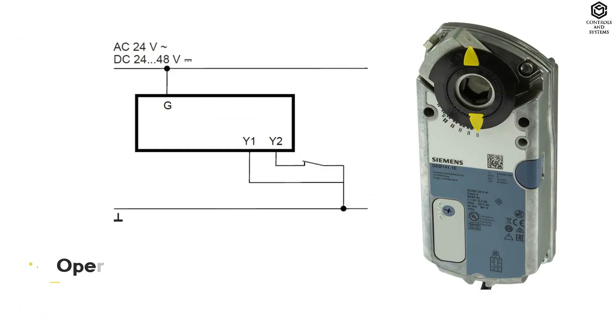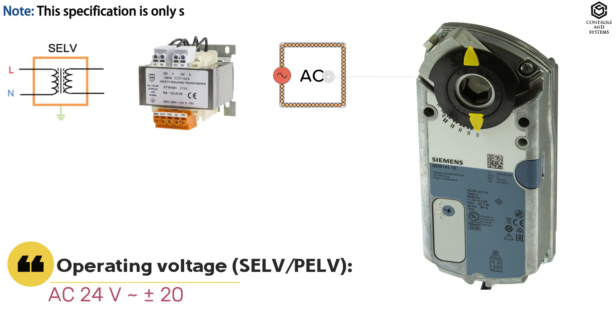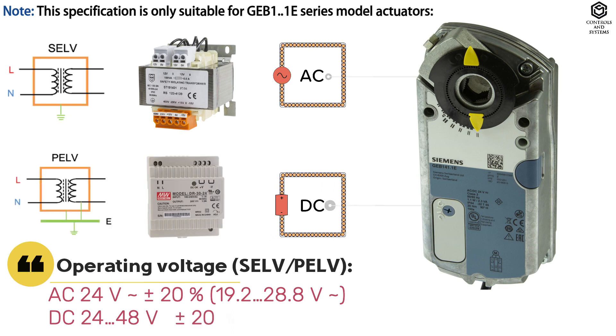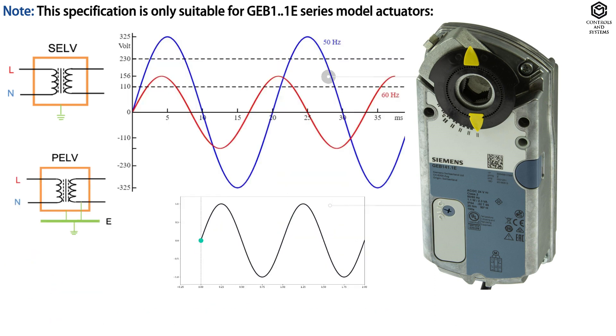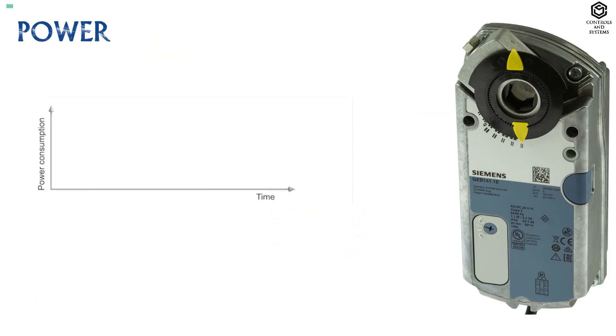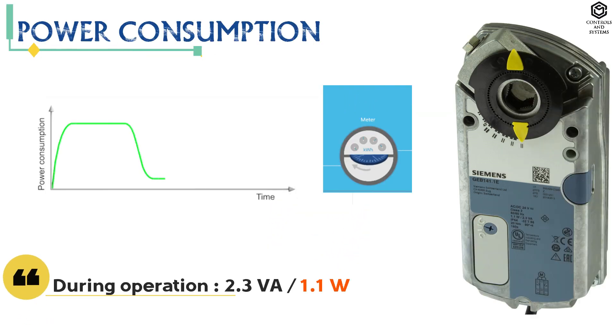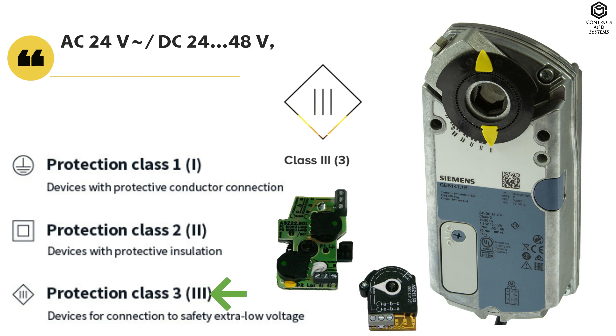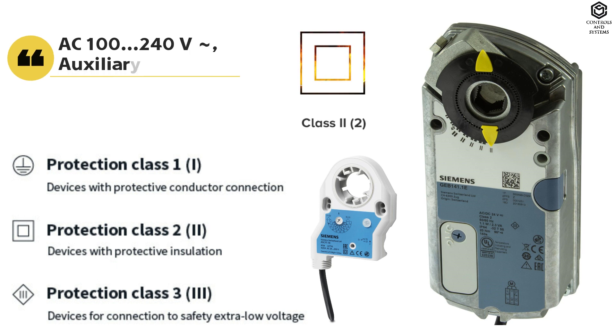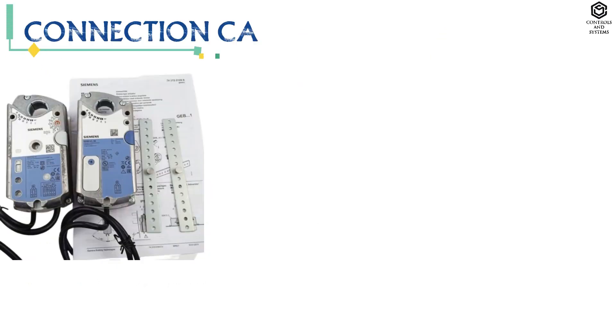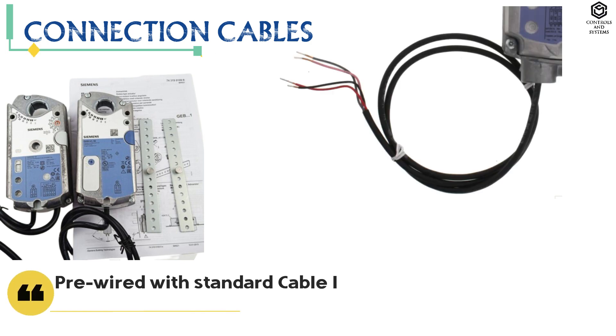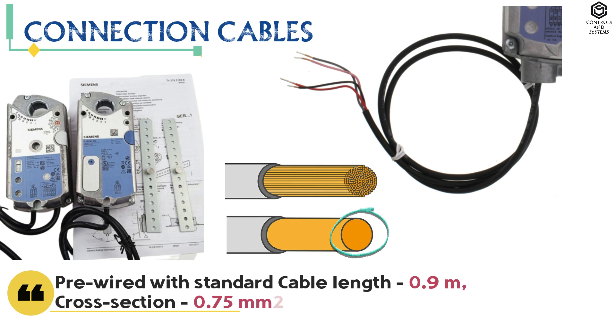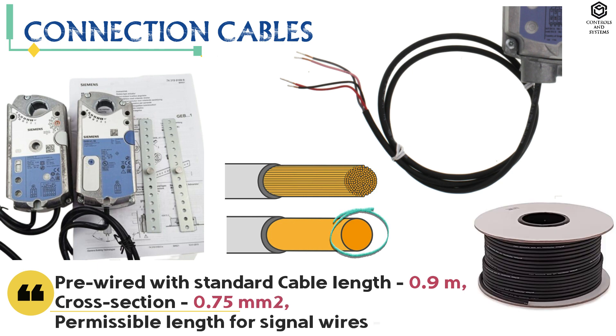Electrical data: operating voltage is AC 24 volt (±20%) or DC 24 to 48 volt (±20%). Frequency is 50 or 60 hertz. Power consumption during operation is 1.1 watt, during holding is 0.5 watt. Protection class of 24 volt feedback potentiometer is 3, and of 240 volt auxiliary switches is 2. Pre-wired with standard 0.9 meters connection cables, cross-section 0.75 square millimeters. Permissible length for signal wires is 300 meters.